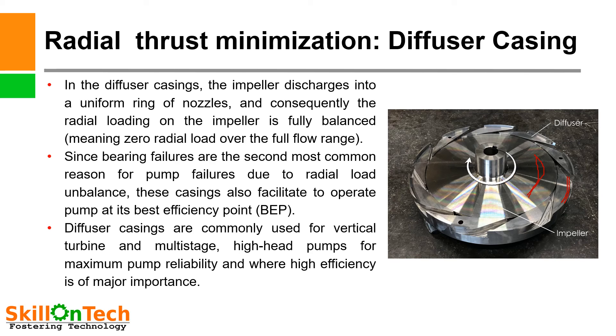As we know, bearing failures are the second most common reason for pump failures due to radial load unbalance. These casings also facilitate operating the pump at its best efficiency point (BEP). Diffuser casings are commonly used for vertical turbine and multistage high head pumps for maximum pump reliability and where high efficiency is of major importance.